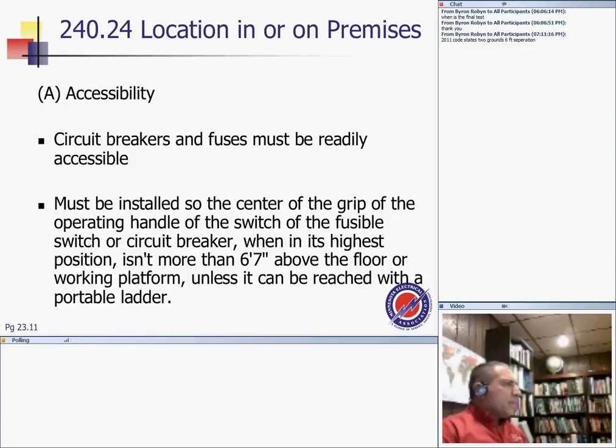Looking at the premises, circuit breakers must be readily accessible when you put them in the premises. You can't put them in a place where they're going to be higher than 6 foot 7 inches. Otherwise, short people like Chad can't access them, and that's true. So put them as you put your panels, guys. This is a big deal.